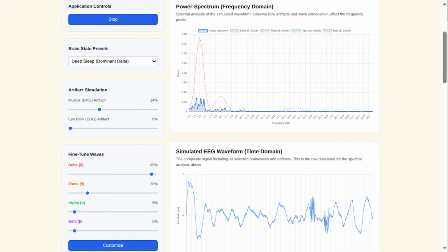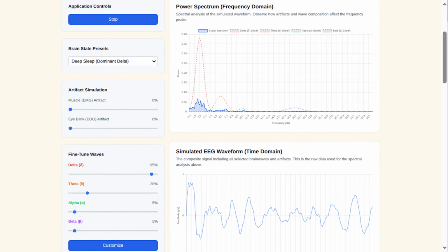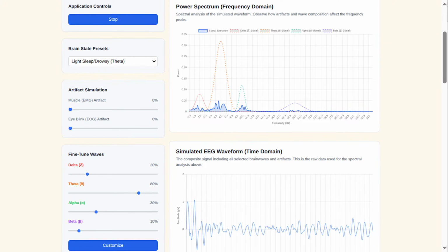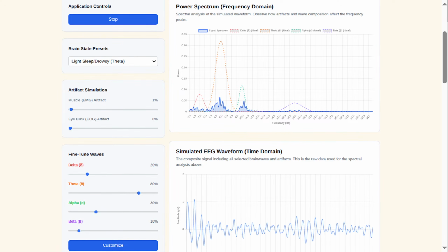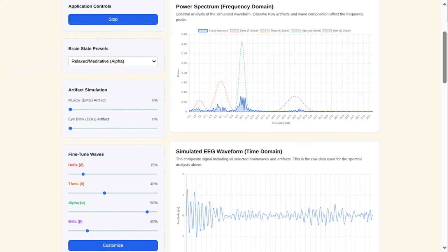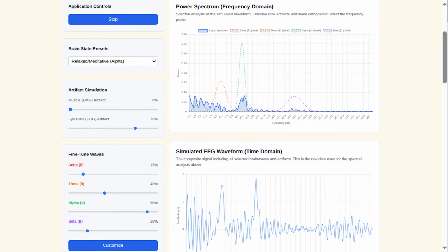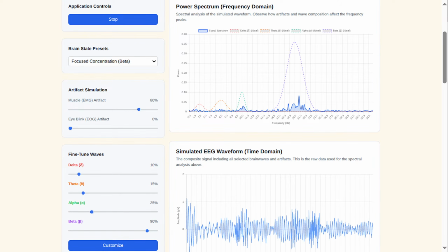Can you talk about the signal quality? Sure, EEG signal quality depends on factors like electrode placement, sensor type, and interference. High-quality recordings use medical-grade electrodes and good contact with the scalp to reduce noise and improve signal clarity. Okay, and how else could you improve the signal to noise ratio? Improving the signal-to-noise ratio can be done by using high-quality amplifiers, reducing muscle and environmental noise, and applying filtering techniques. Proper skin preparation and the use of active electrodes can also further enhance the clarity of the EEG signal.